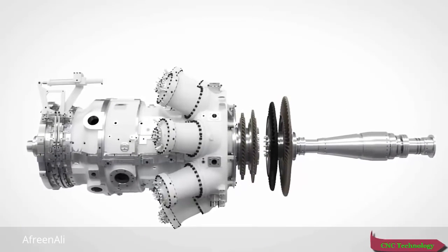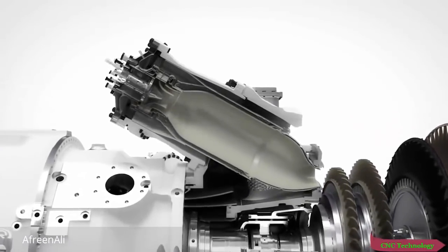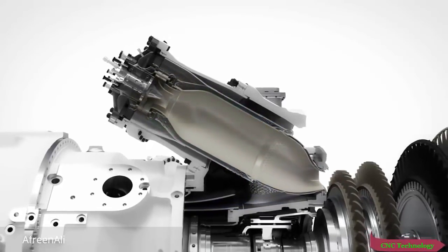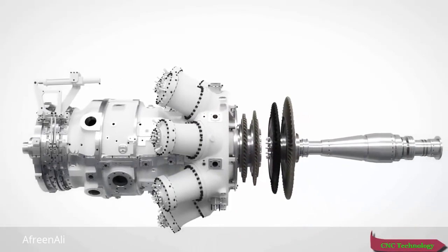The new combustor. Featuring the fourth generation of DLE burners from Siemens. The burners are designed to further increase the power turndown range compared to its predecessors, maintaining NOx and CO emissions well within legislation levels. The DLE turndown capability enables the use of large single turbines, replacing multiple small units, allowing the same operating envelope. It offers robust and stable operation with dual fuel online switchover capabilities.